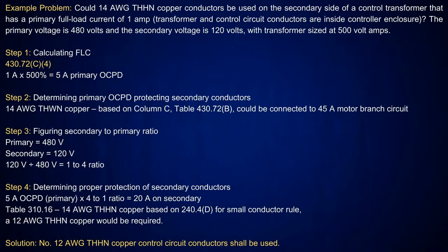All right. Now this one, you'll know this one because we actually get into this where we're dealing with motors in 430.72(C)(4), and they're basically going to clarify exactly what you're allowed to do. All right. Now, when you come in, they're going to ask, could 14 AWG THHN copper conductors be used on the secondary side of a control transformer that has a primary full load current of 1 amp? This is your transformer and control circuit conductors are inside the control enclosure. The primary voltage is 480 volts and secondary voltage is 120 volts with transformers sized at 500 volt amps.